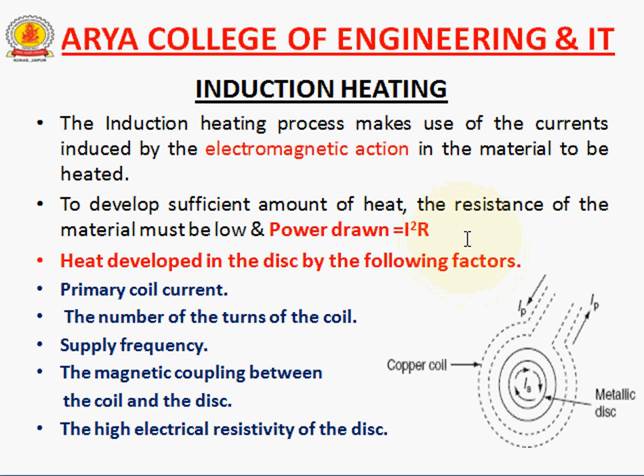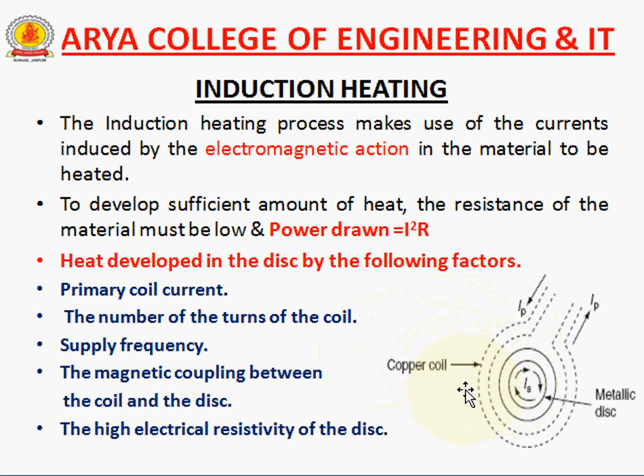To develop sufficient amount of heat, the resistance of the material must be low, and the power drawn is generally the power loss I²R. The heat is produced due to the following factors: the primary coil current, the number of turns of the coil, supply frequency, the magnetic coupling between the coil and disc, and the high electric resistivity of the disc. When current flows through the copper coil, heat develops by the help of electromagnetic action in the material to be heated.